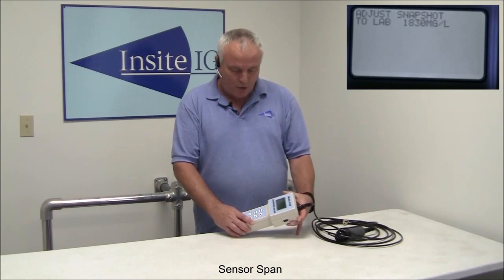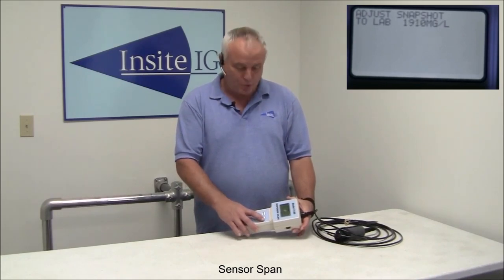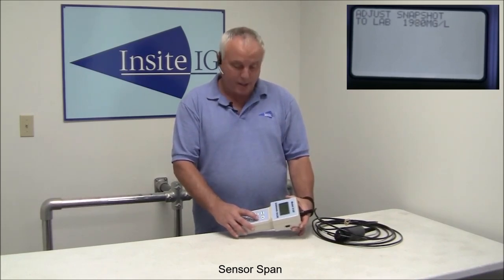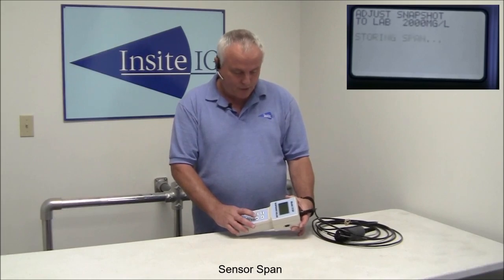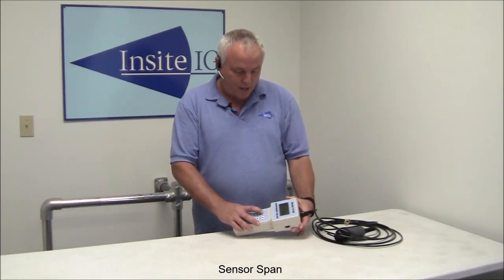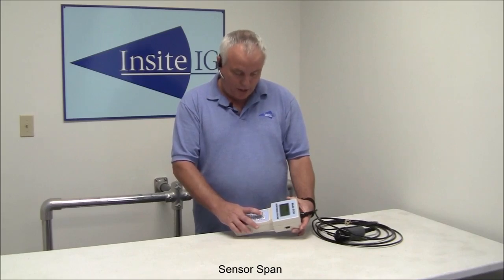And it's going to come up with the number that it thought it was when you took the snapshot. All you have to do at this point is use the up-down arrow keys to make it agree with the result that the lab came back. So you just move it up and down until it gets to where it needs to be, press enter. It'll say storing, and then you're done. You press menu, go back to run, select enter, and you're back in the run mode. That's all there is to it.